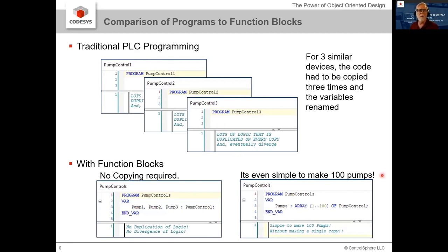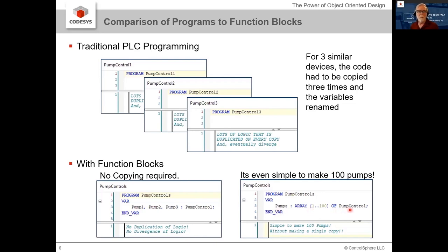With function blocks, we just put our programming into a function block, take all those global variables and put them inside the function block itself. Then we can create three instances — pump one, pump two, pump three of type pump control — just like declaring three instances of an integer. No copying global variables, no renaming, no naming convention, no copying programs, no having code in multiple places. If we want 100 pumps, just put it into an array of 100 pumps and you're done.